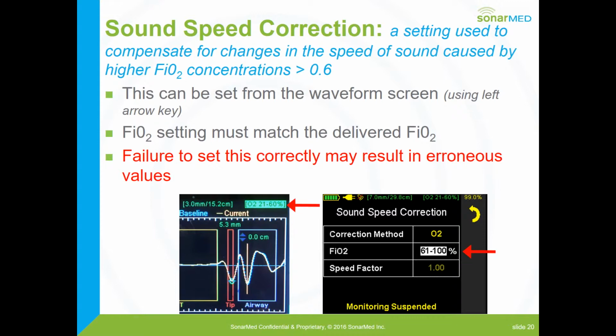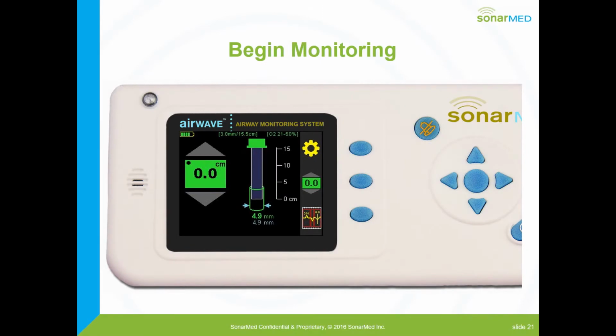The waveform screen is where it's the easiest to do, and it's very similar to setting your tube length, and you just have a few pushes of the buttons and you're able to set that and change that. The only time you need to do that is if you place your baby on above 60% for an extended period of time. So if you're just giving them a little extra oxygen while you suction, you would not make changes there. So once we've looked at all that, we're going to begin monitoring. And this next slide, you're actually going to see a video.